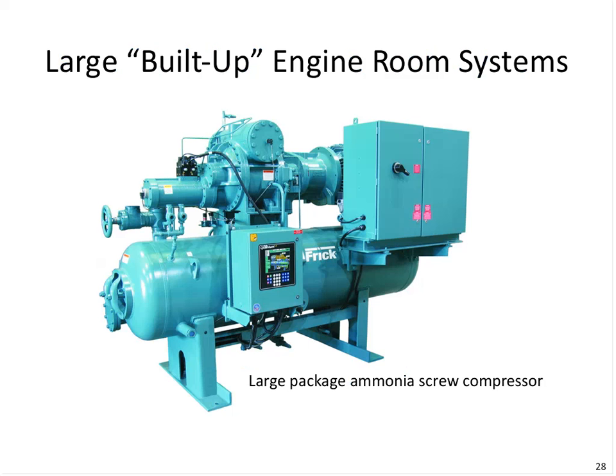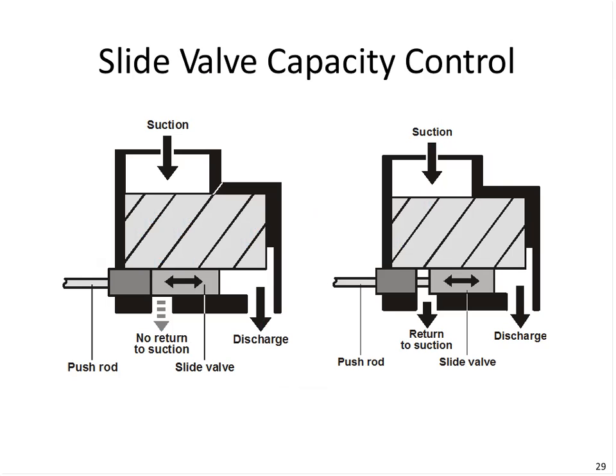And the last thought here that we would like to show is the impact of having variable speed on the compressor. Of course, we still may use the slide valve in conjunction with variable speed. And the slide valve here allowing gas to be returned to the suction. So here we see the slide valve actually actuating, and some of the refrigerant vapor is drawn from out of the rotors before it's compressed and allowed to come right back to the suction again. So we can adjust this slide valve to get any quantity of refrigerant to be compressed through the rotors.